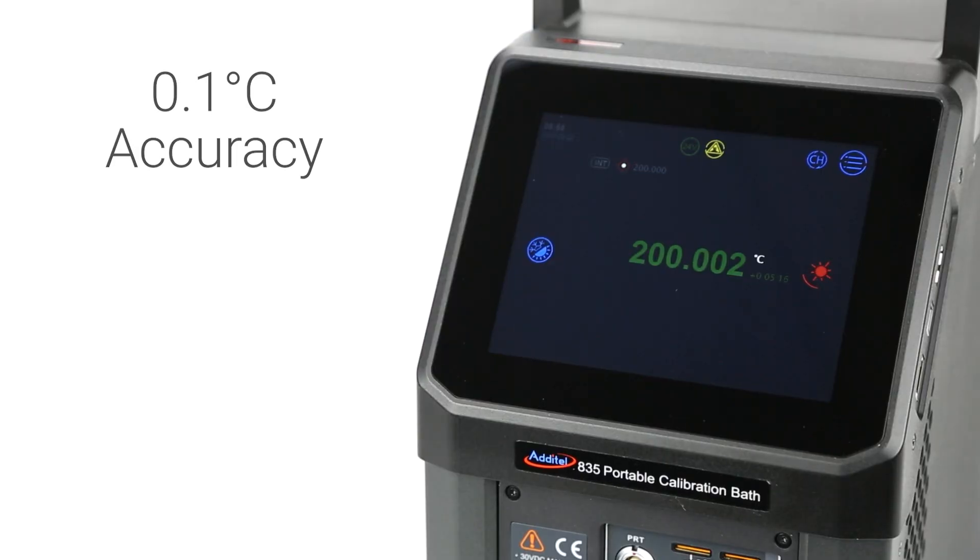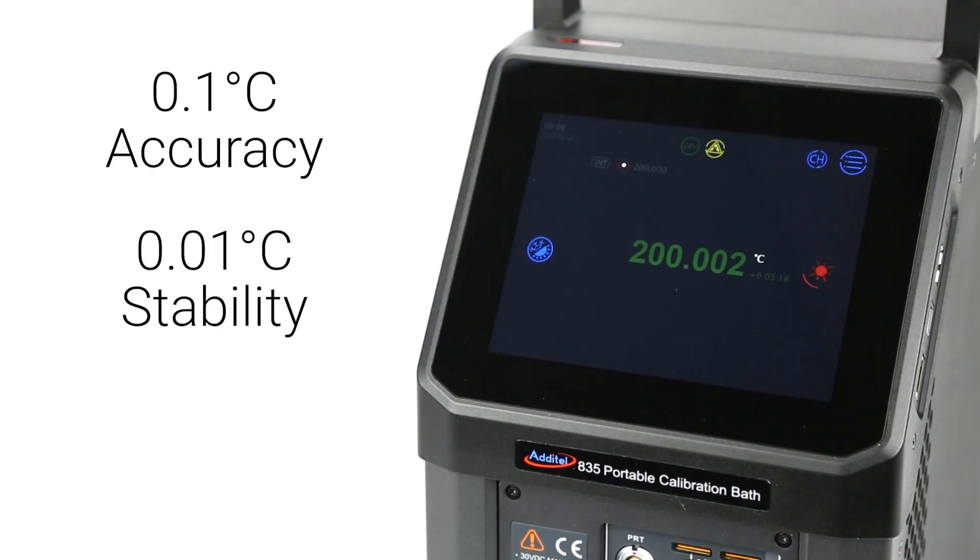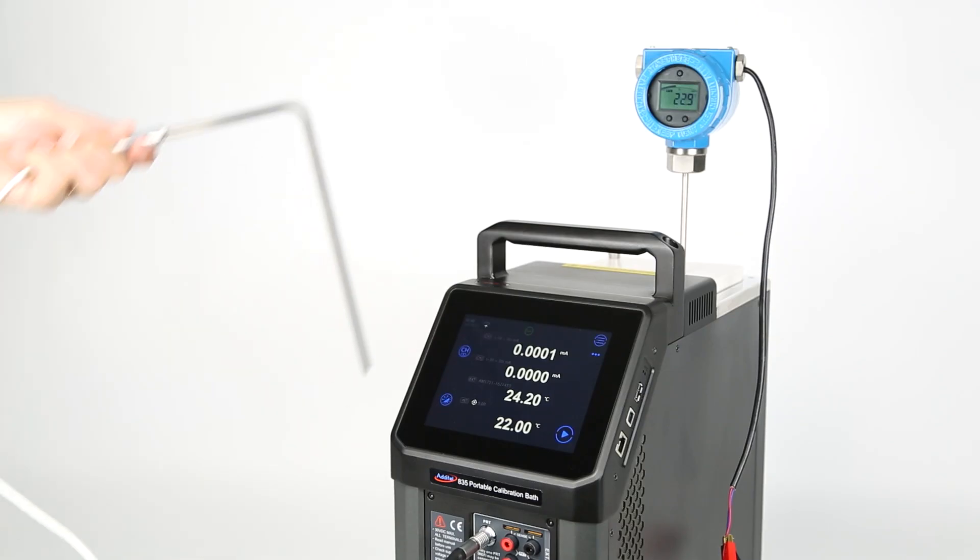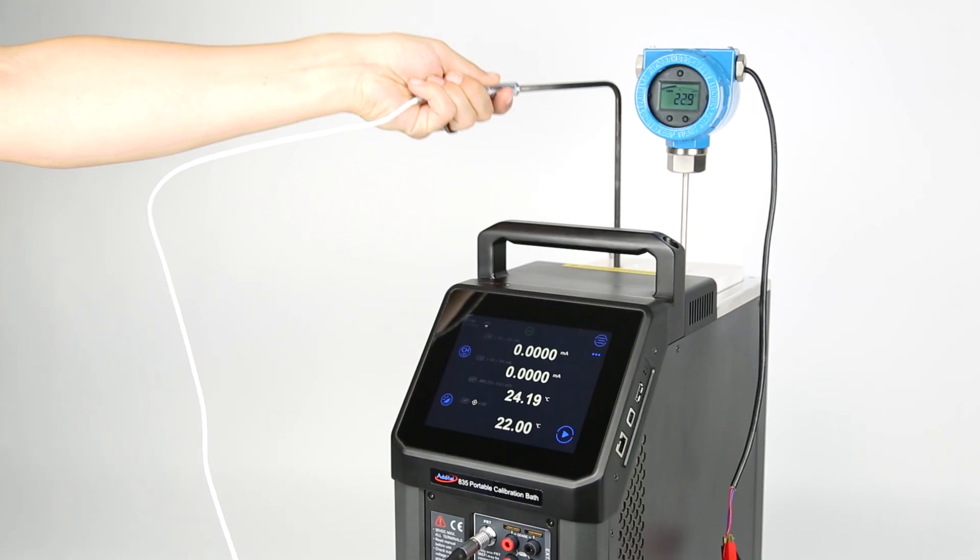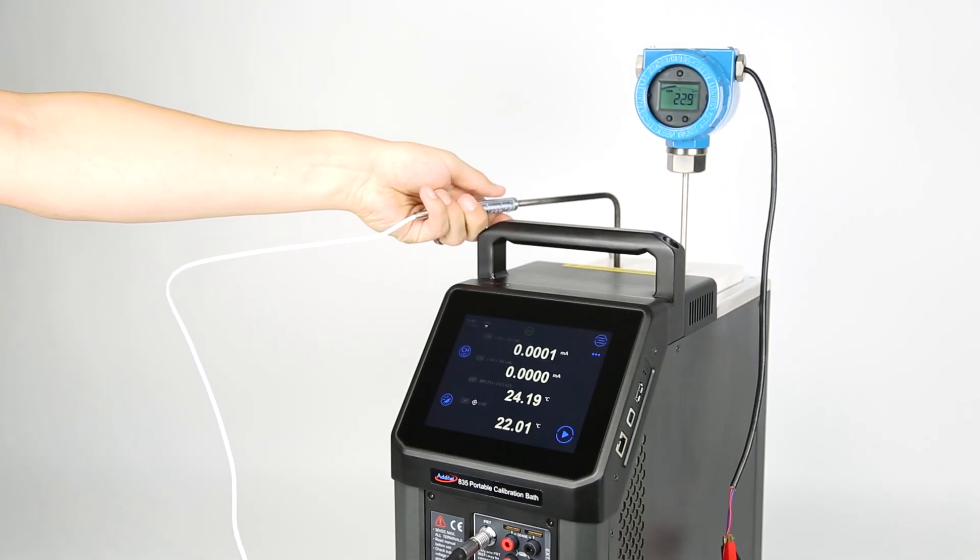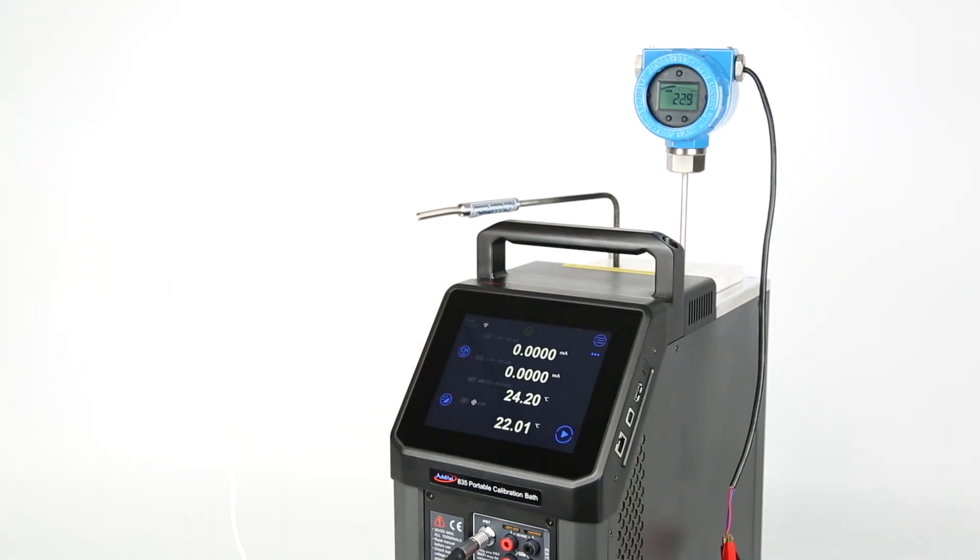With a display accuracy of 0.1 degrees, a stability of 0.01 degrees, and a uniformity of 0.02 degrees, the 835 generates a uniform temperature field to ensure repeatable and reliable results across a wide range of sensor types and sizes.